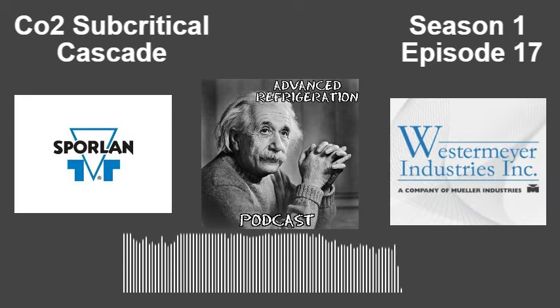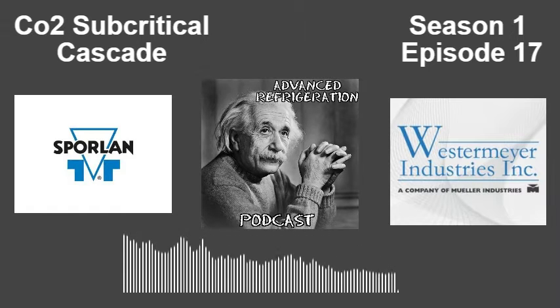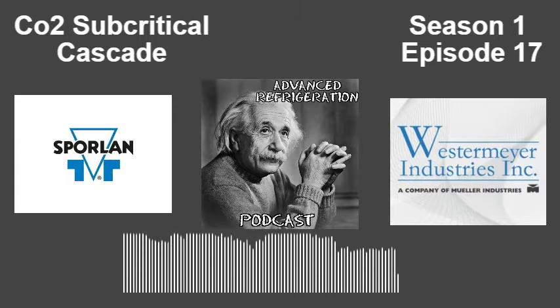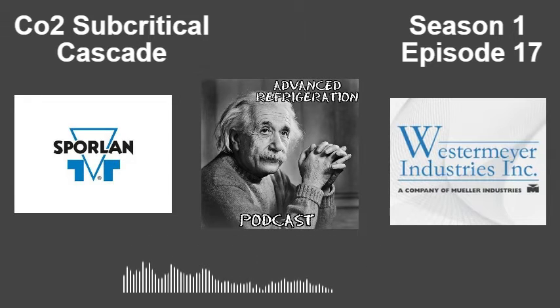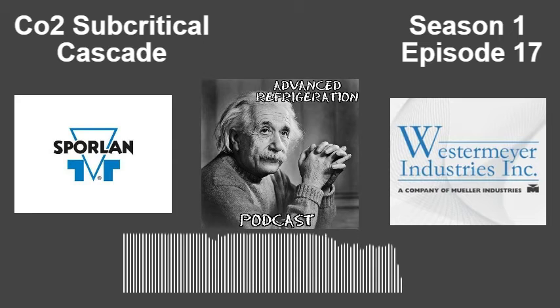So a couple things that you touched on. Just for example, you were talking about the liquid being created. One of the things I have seen, we had a store that had a desuperheating coil that was outside, basically up on the roof. The fan would just turn off and on based off demand, based off of pressure. In the middle of winter, what would end up happening is exactly what you were talking about.